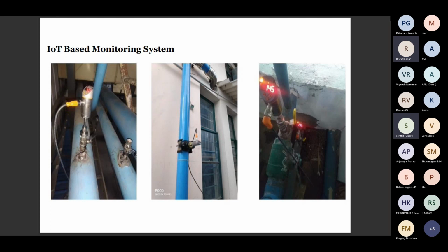For example, if your company is running a 50 HP compressor, which may be more than 5 years old, it's a screw compressor. As per the OEM commitment, the compressor will be generating nearly 220 CFM. Whether this 220 CFM is being generated or not, you can monitor using this IoT system, and also what your air demand inside the plant is. The same system can be used for leakage also. At lunchtime, maybe 12 to 12:30, the machines and auxiliary equipment are not used. The whole foundry is not operating except melting. During this time, the air leakage quantity in CFM can be arrived at using the system.